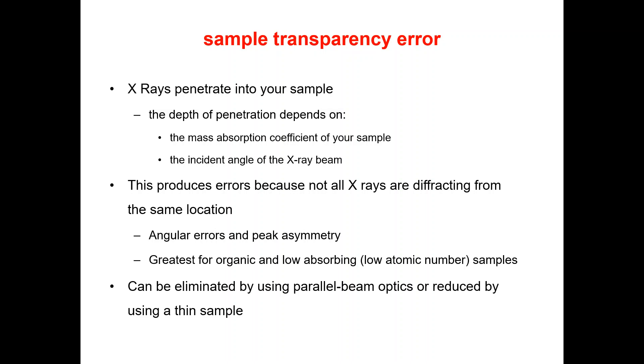The solution for sample transparency error is that it can be eliminated by using parallel beam optics, or it can be reduced by using a thin sample. Using parallel beam optics or a thin sample is the key approach to eliminating many errors in XRD analysis. The best practice while analyzing your sample in XRD is to use a thin sample and the proper optics or proper slits.